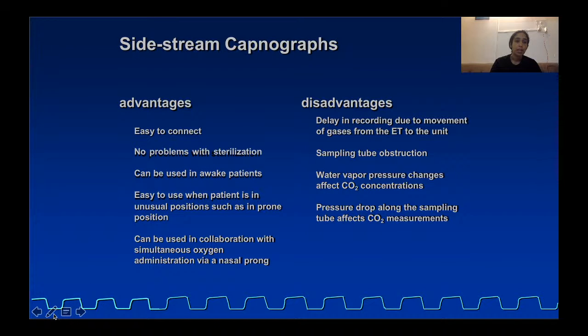Now, advantages and disadvantages of your side stream. It is very easy to connect, no problems with sterilization, and can be used in awake patients. It just has to be attached to the face mask or the nasal prongs. It is easy to use when the patient is in unusual positions such as prone. In intubated patients, it is connected after the ET tube, after the filter. It can be used with simultaneous oxygen administration via nasal prongs. However, because oxygen is not absorbed, it can decrease the waveform, so oxygen can cause some interference.